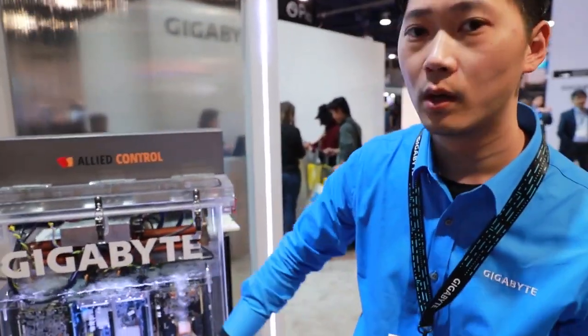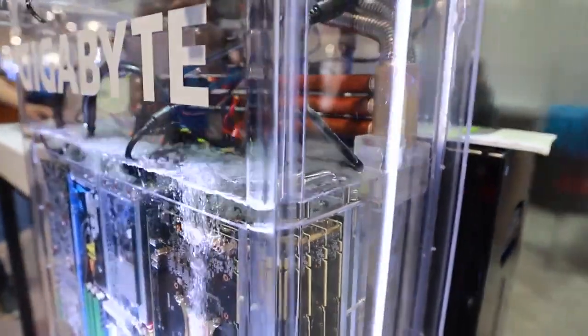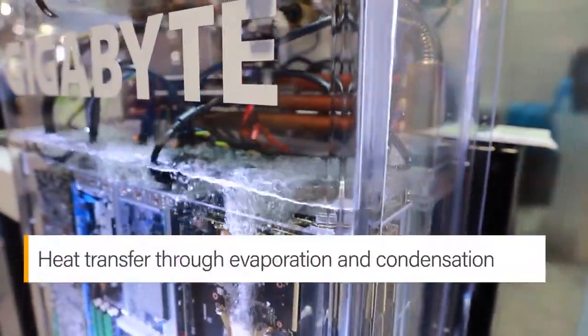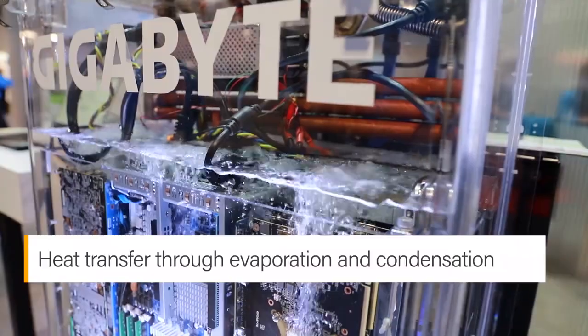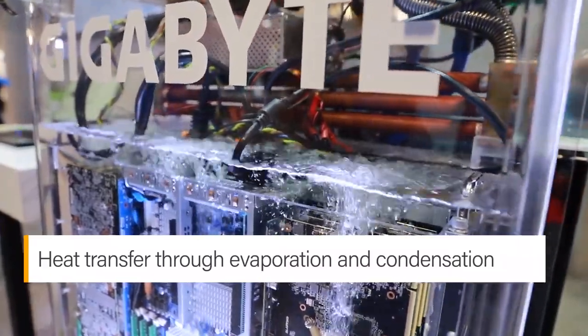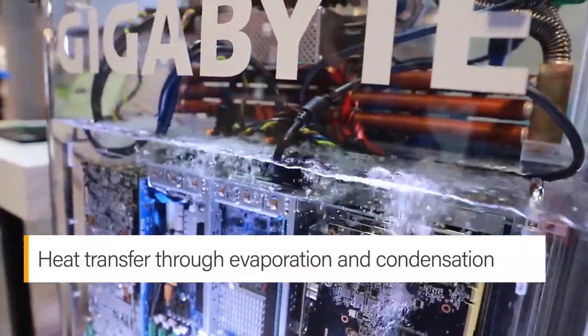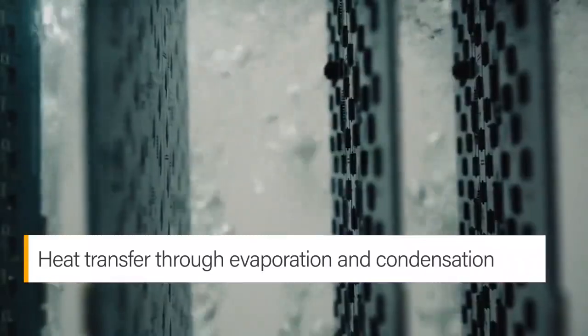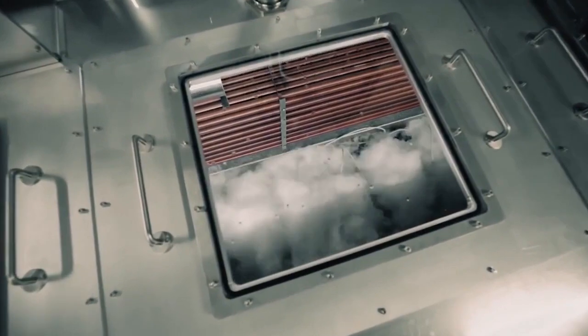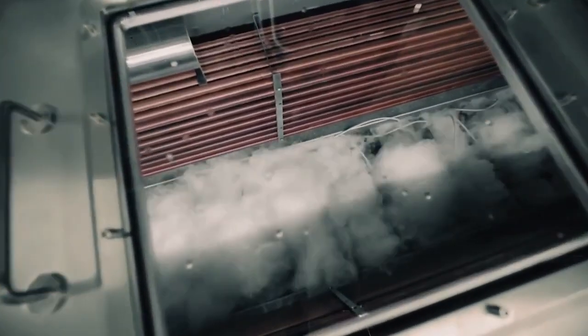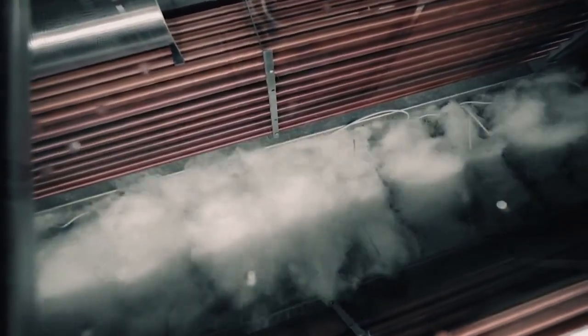So why do we call it two-phase? We submerge the server into the tank, which is filled with 3M Novec engineered fluid, and the heat transfers by evaporation and condensation, therefore we call it two-phase. The fluid is not water, it is the electrochemical fluid made by 3M, which is non-conductive and non-corrosive, and only has a constant boiling temperature of 56 degrees.